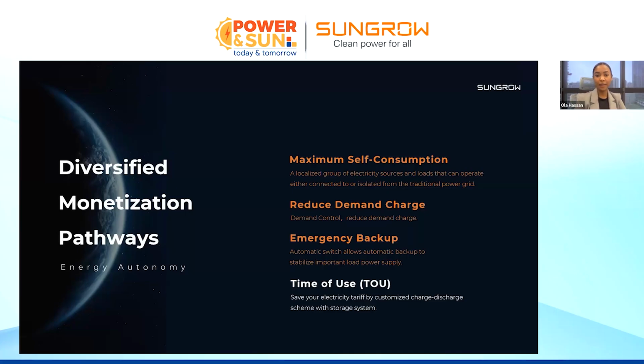Time of use, and this is specifically for countries where there are specific peak hours when the electricity price goes up. For example, from 12 to 2 p.m. Perhaps that's a peak hour where most of the electrical consumption happens and users are using their home appliances. So the electricity price increases between 12 and 2 p.m. We can set up the system and schedule it to work based on the time of use. So for example, from 12 p.m. to 2 p.m., the system can inject and discharge electrical power from your battery to your load. And perhaps there is an off-peak time as well. During the night time, there's not a lot of electrical consumption. So if the electricity price comes down again, we can charge the batteries from the electricity grid. So over here again, the electricity grid is stable. However, according to the peak timings, the tariff rates are changing. So all of these applications can be met using Sungrow C&I systems.